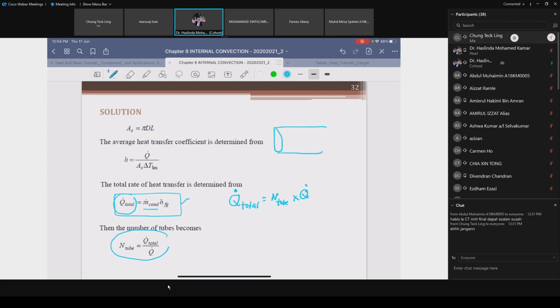You can see the tube, the water flows into the tube and then the Q is m Cp delta T. Understand? This is the Q of water, liquid. You know, because in the heat exchanger, steam comes in. Then the water's heat due to the steam, you have calculated, right? So that 2431 is the hfg of the steam, not of the water inside the tube.